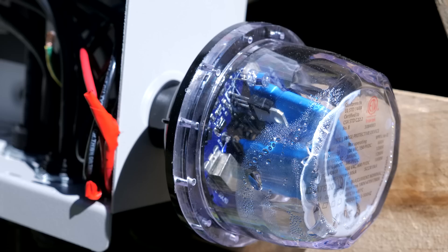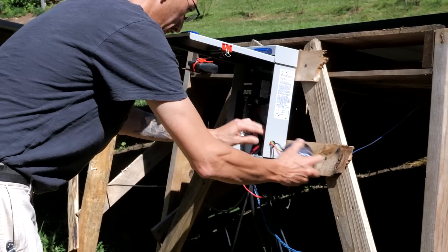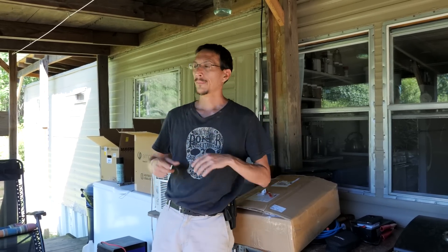The other thing that went bad was one of the surge protection devices on the second array had condensation in it — it was not sealed from the factory. You don't want condensation in there because it can eventually corrode and cause your voltages to do weird things. That's also in this box. Again, Midnite Solar — double thumbs up, amazing company. That's why they have such a great name in the industry.